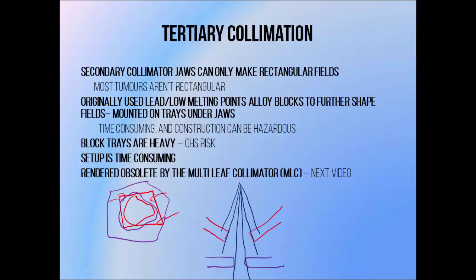You also need to make a block tray for each beam, and each patient treatment involves several beams, so it requires a lot of trips into the treatment room to change blocking trays. The blocks are also quite heavy, which can be an occupational health and safety risk to staff and a risk to the patient as well since they hurt a lot when dropped. You can get quite good results using custom blocks, but they've been largely rendered obsolete by the invention of the multi-leaf collimator, which will be covered in detail in the next video.